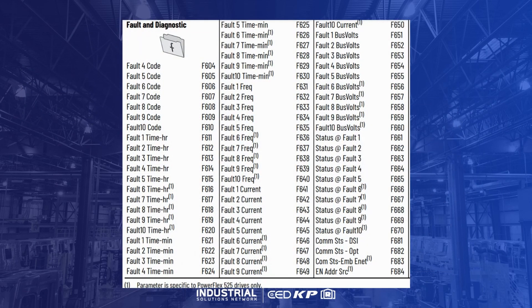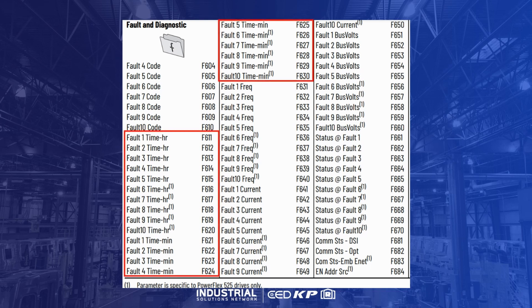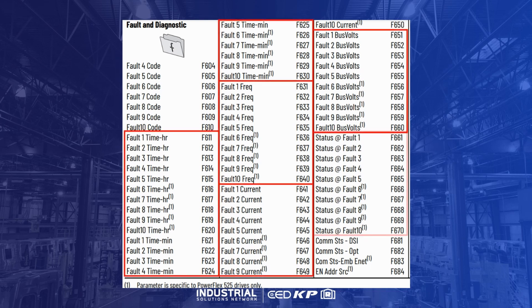Following the fault code IDs, the next set of parameters provides timestamps, frequency, output current, bus voltage, and drive status. For the PowerFlex 523, the five most recent faults have parameters for their associated data, while for the PowerFlex 525, all 10 recorded faults will have parameters for associated data.